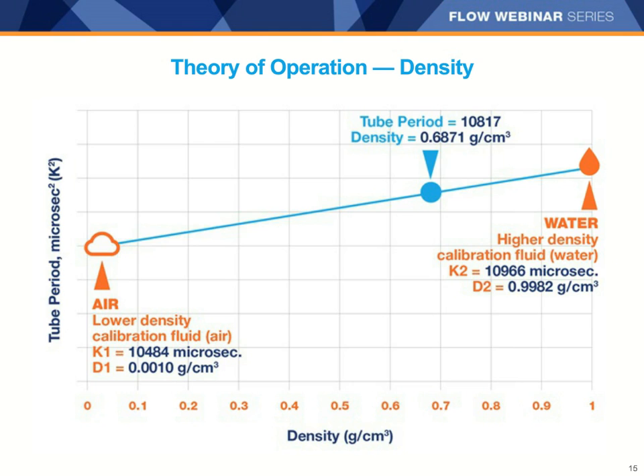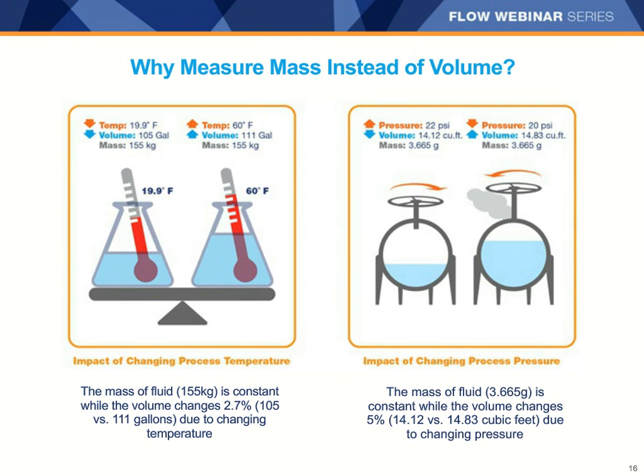In other words, if the tube period is 10,817 microseconds, as the example shows above, then the transmitter knows that the fluid density must be 0.6871 grams per cc to a high degree of accuracy. Micro Motion meters can perform as good as plus or minus 0.002 grams per cc on density measurement. Micro Motion performs the initial density calibration in the factory. Field calibrations can also be performed using air, water, or virtually any process fluid with a known density.